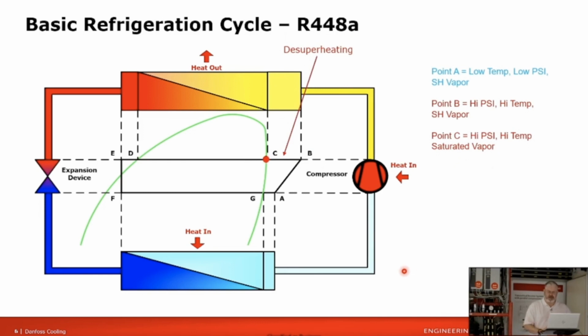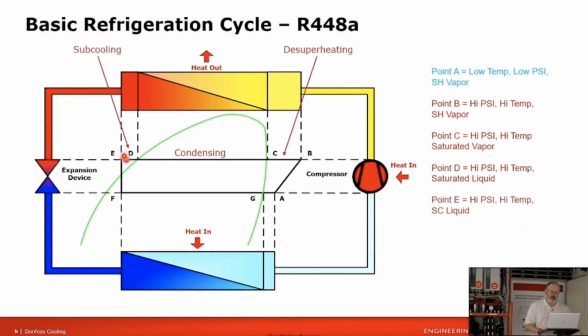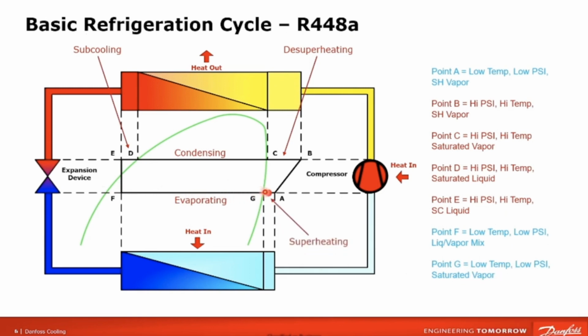The first few passes through the condenser, we desuperheat. And then we hit the saturation curve. We continue through the condenser, where we condense back to a saturated liquid. And then by point E, we'll have subcooled a few degrees, and we'll be a high pressure, still high temperature, but subcooled liquid. And then we go across our expansion valve. That's the separation from the high side of the system to the low side, much in the same way that the compressor separates it as well from suction to discharge. So we go across the expansion valve, we enter the evaporator, we flash off a little vapor here to cool down the remaining refrigerant. Then we go through the evaporator where we boil off the refrigerant until we're a saturated vapor. And then we superheat a little before we enter the compressor to make sure no liquid makes it back to the compressor.